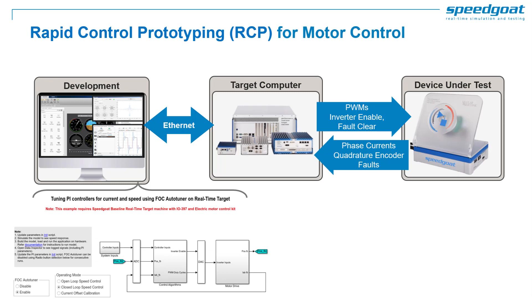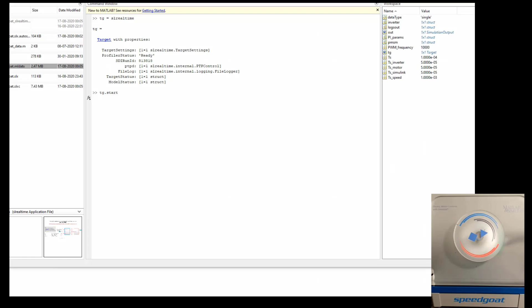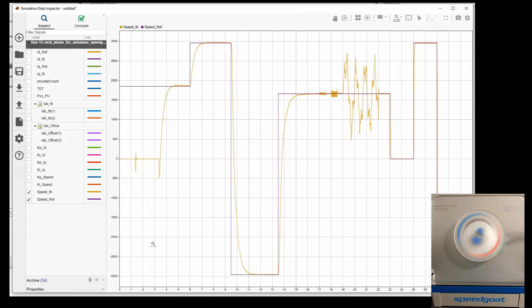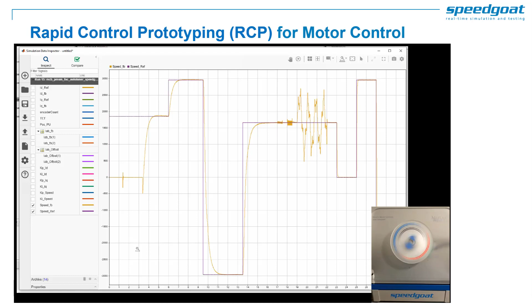As an example, you can use the FOC Auto Tune feature to optimize speed and current control loops. In this short video, the feature adds some disturbance on the RPM signal of the spinning motor. Thereby, the P and I gains of the controller are optimized based on the desired system response. As you can see, the response of the motor is much faster after tuning, but doesn't overshoot either.